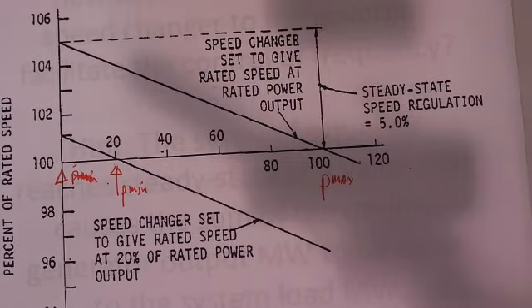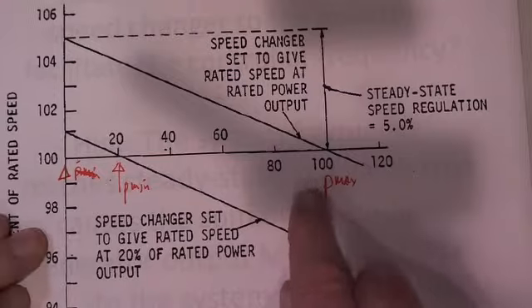Generators do not operate down to 0. They do not operate at a power output less than, let's say, 20. That's a reasonable assumption. And they can't operate above 100. What limits the power output of the generator? Well, the capacity of the generator to handle current at its rated voltage will determine how much power output. And so will the fuel handling equipment, the boiler, and the steam turbine. They're all designed to operate up to a certain max, and beyond that you're not. Everything is designed around that design point for so much power output.